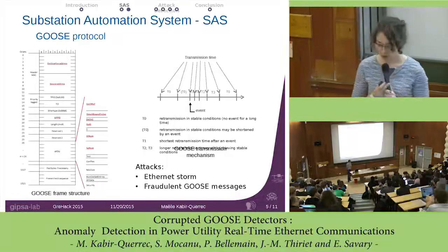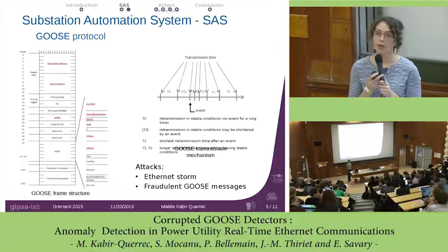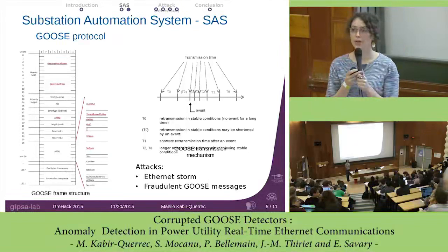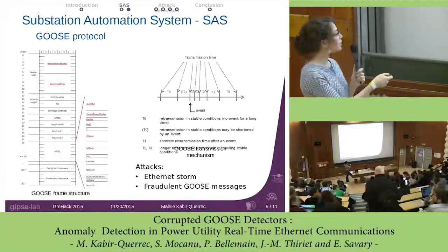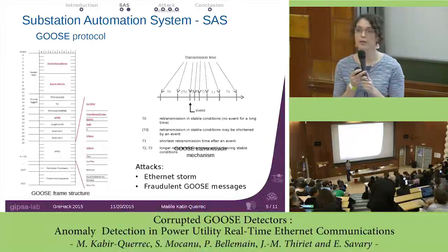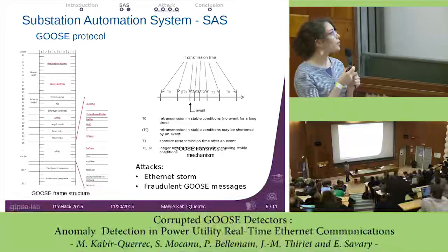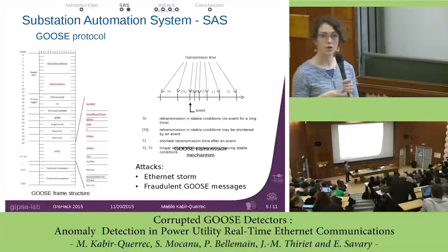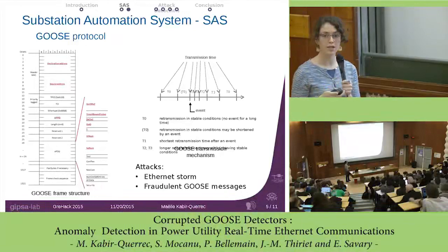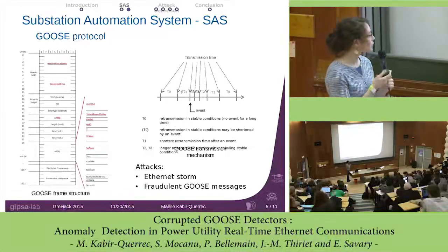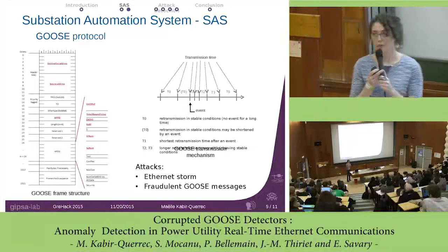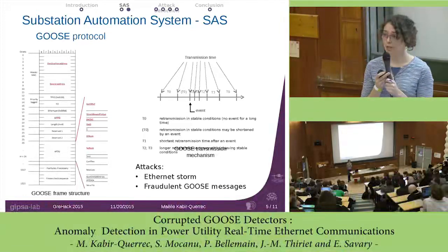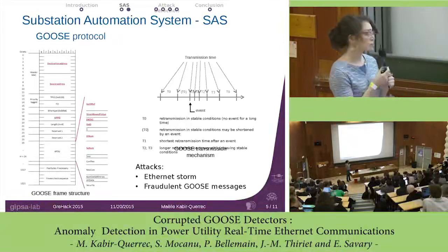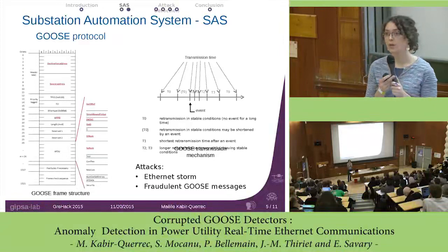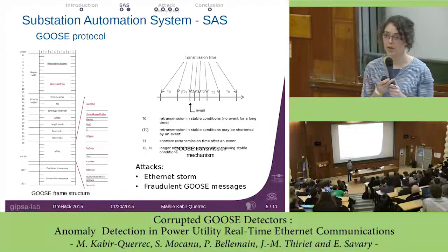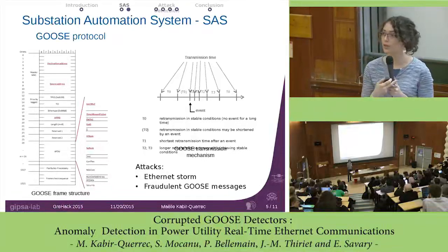State number. So state number is incremented every time a data of the dataset changes and requires to send a GOOSE message. And sequence number is set to 0 when a state number is incremented. And then when the message is sent over and over, it will be incremented for every iteration of this message with the same content. I will explain it a bit further. I must mention also the security field, which is defined in the standard, but the standard doesn't give any further explanation about the use we must do of it. And actually, for instance, the IEDs we have on our experimental platform, Siemens Siprotec 5 line, do not use this security field.